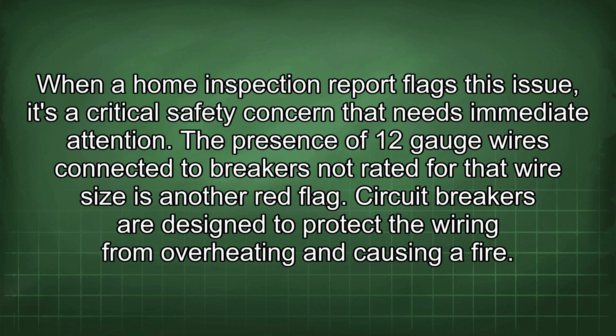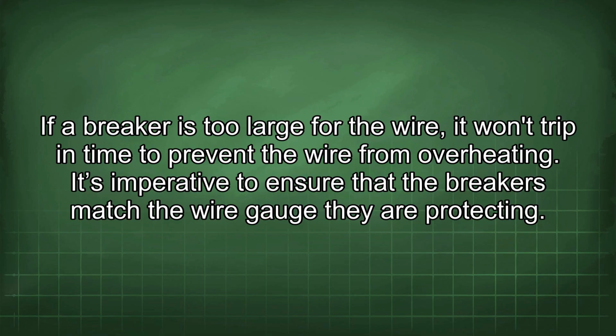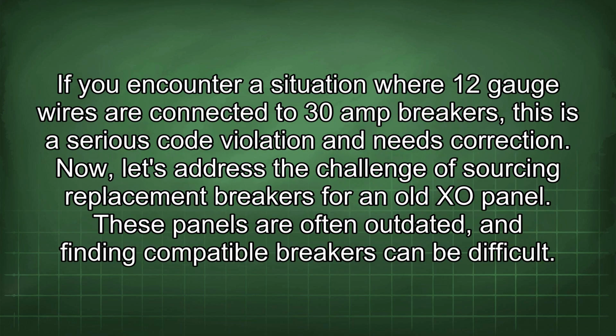When a home inspection report flags this issue, it's a critical safety concern that needs immediate attention. The presence of 12-gauge wires connected to breakers not rated for that wire size is another red flag. Circuit breakers are designed to protect the wiring from overheating and causing a fire. If a breaker is too large for the wire, it won't trip in time to prevent the wire from overheating. It's imperative to ensure that the breakers match the wire gauge they are protecting. If you encounter a situation where 12-gauge wires are connected to 30-amp breakers, this is a serious code violation and needs correction.